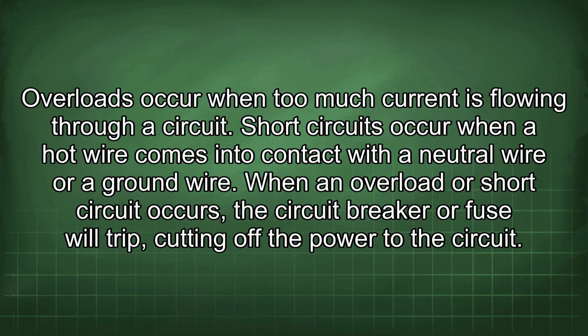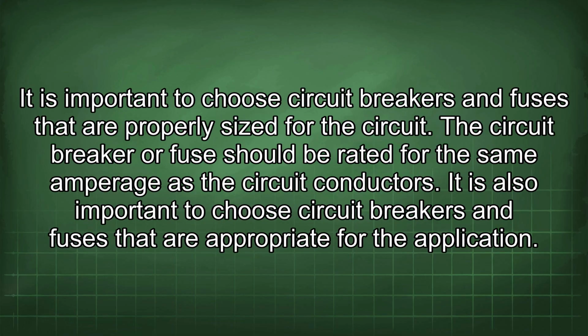When an overload or short circuit occurs, the circuit breaker or fuse will trip, cutting off the power to the circuit. It is important to choose circuit breakers and fuses that are properly sized for the circuit. The circuit breaker or fuse should be rated for the same amperage as the circuit conductors. It is also important to choose circuit breakers and fuses that are appropriate for the application.